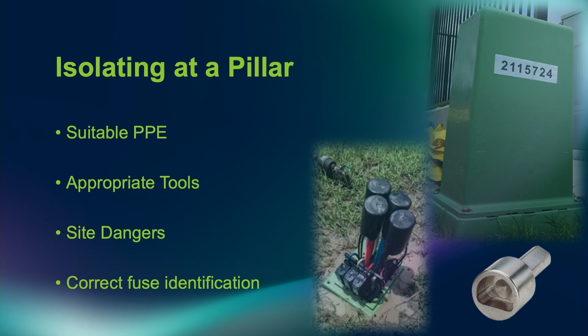Now, some adequate PPE will be required, just like with the poles, and at a minimum, you should have a tested insulating mat with your insulating gloves and leather outers again, and perhaps a face shield should be required at this point. Now, you may need a safety observer as well, depending on the complexity of the task and your on-site risk assessment. Some additional tools that you might require would include a pillar box D-bolt socket or T-bar to open the pillar. We've got those unique shaped bolts on the pillars. And you'll need a clamp meter for your circuit identification.